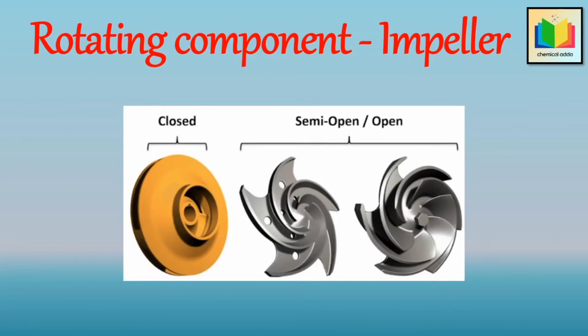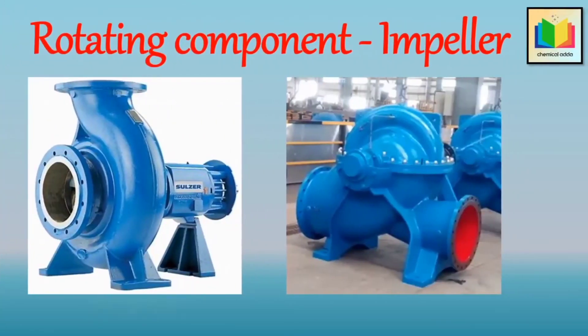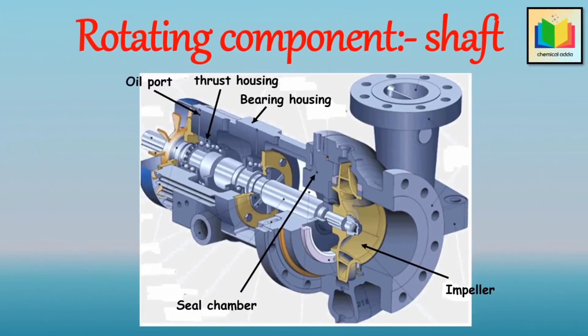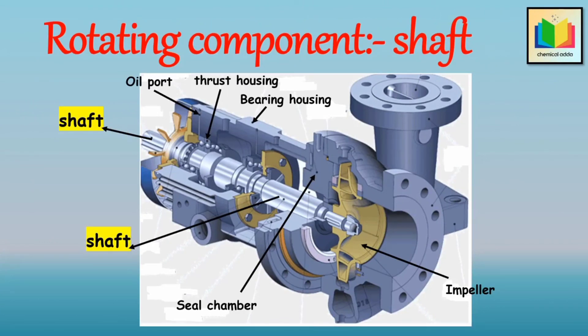Open or semi-open type impellers are used for viscous liquids or liquids containing solid materials, and on many small pumps for general service. Impellers may also be of the single suction or double suction type. If liquid enters from one side, it is a single suction type; if liquid enters from both sides, it is a double suction type. The next rotating component is the shaft, whose basic purpose is to transmit torque when the pump is started and during operation, while supporting the impeller and other rotating parts.